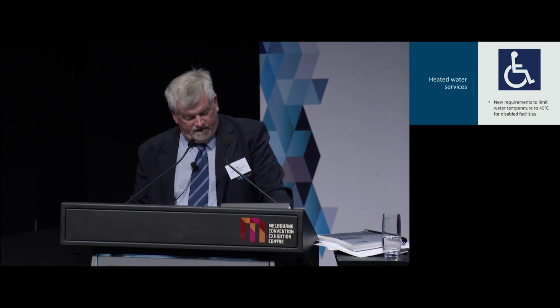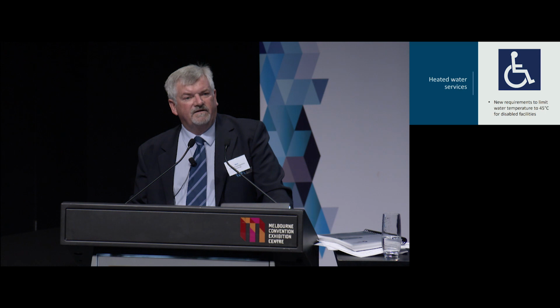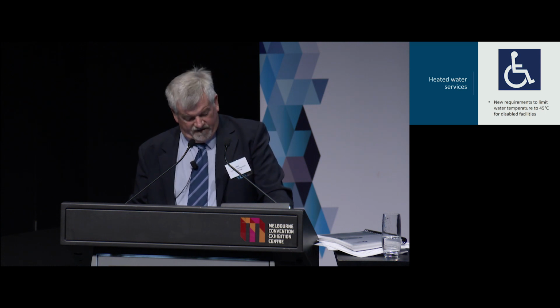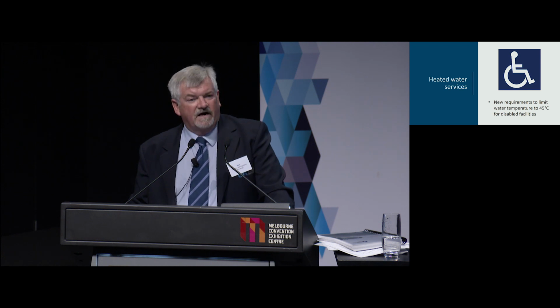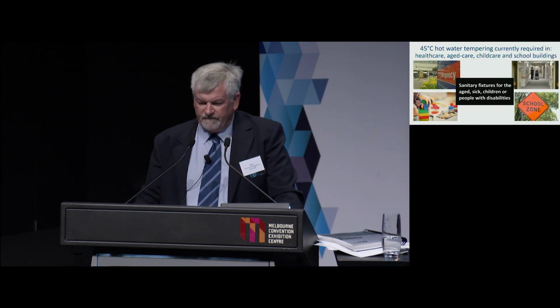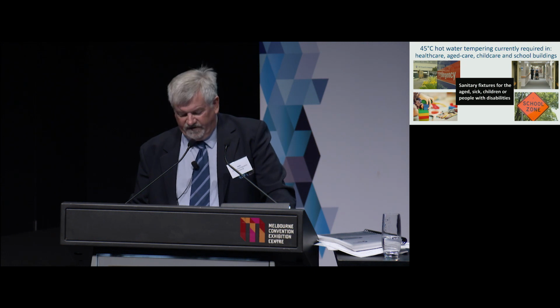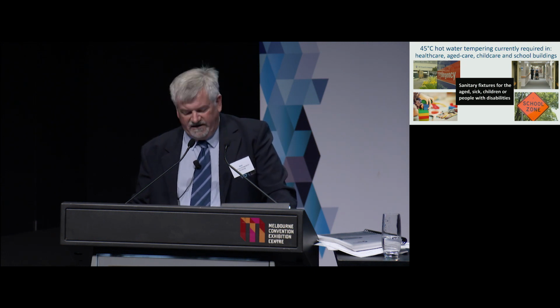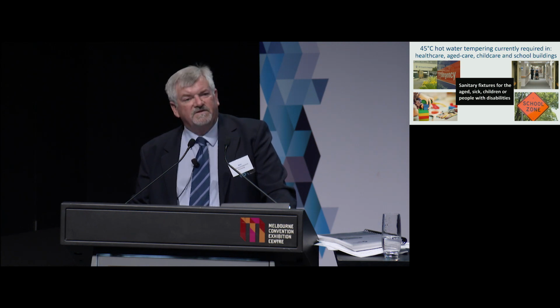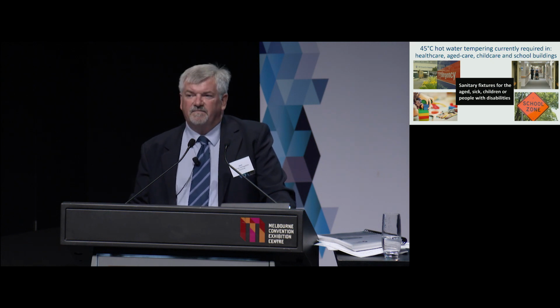Now, there are new requirements for the supply of heated water, with delivery temperatures limited to 45 degrees C in accessible facilities in buildings for people with a disability, that has been expanded in the 2019 version of the National Construction Code PCA. There are now more classes of buildings where this is a requirement, and you need to be clearly aware of these requirements and changes. AS/NZS 3500 Part 4 requires water temperatures to be delivered at 45 degrees at sanitary fixtures used by the aged, sick, children or people with disabilities in healthcare and aged care buildings, nursing homes, early childhood centres, primary and secondary schools or any other similar facility.